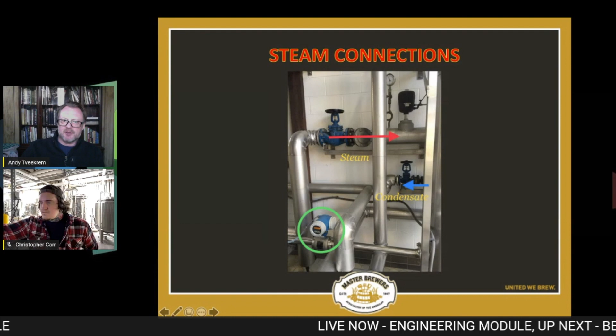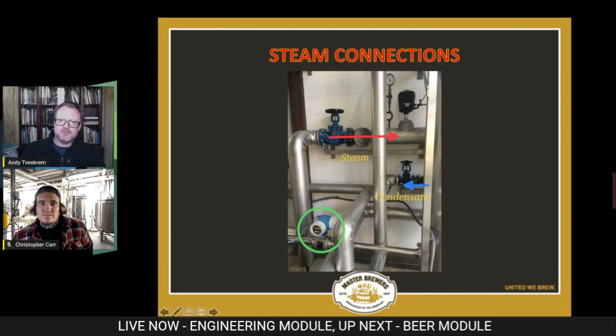And that's also important because it keeps your temperature low, right? With a 15 psi steam chart, I think that's about 230 degrees, something like that. If you're boiling at 212, the delta T there is pretty low. So you're not going to get a lot of scorching. You're not going to get a lot of baked on solids because of that. And also because you're pumping through this system, the wort's constantly moving. So you don't have the issue of the steam sitting there just baking the stuff on. It's constantly being scrubbed away. So these things tend not to foul up too much if you take care of them. And I think that's a nice thing as well.